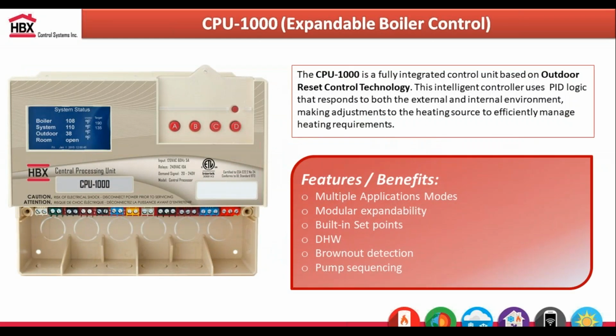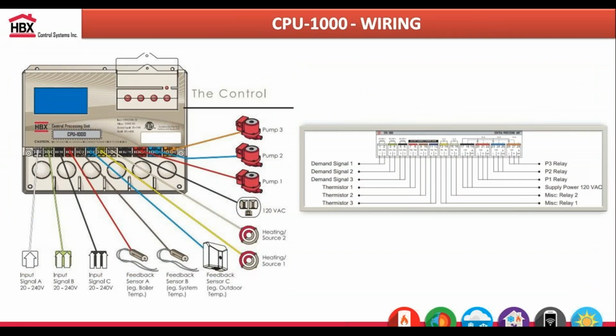So the main unit itself, again, can do 2 on and off boilers and control up to 3 pumps. So you can control up to 2 system pumps as well as a domestic hot water pump. You do have domestic hot water capabilities with all our boiler controllers. It has built-in brownout detection. We have pump sequencing as well on the 1000 series. We give you line voltage for those pump contacts already, so you don't have to put in junction boxes or anything like that. You're already getting 120 volts coming out of those contacts.